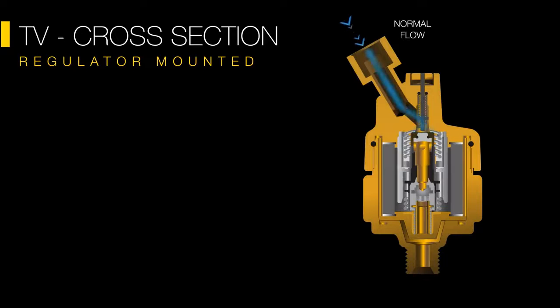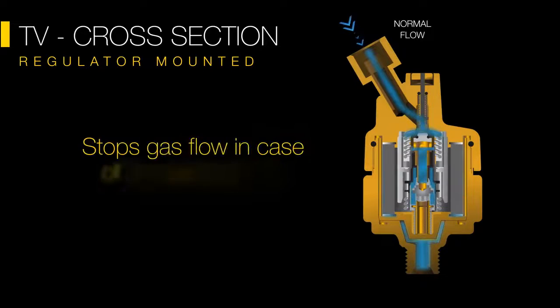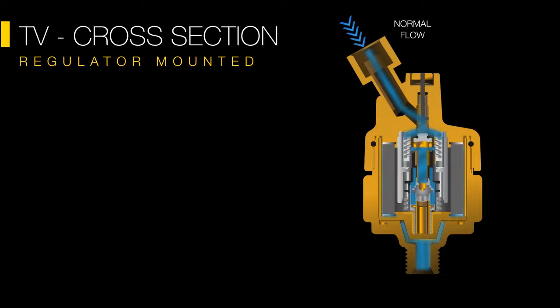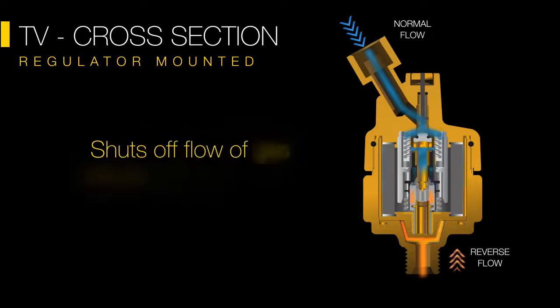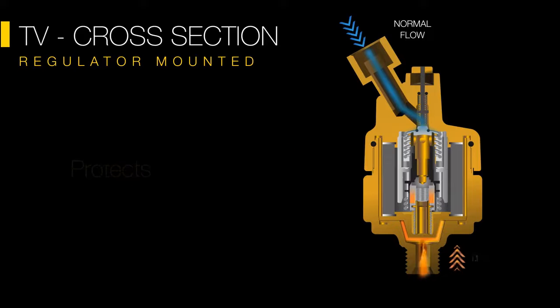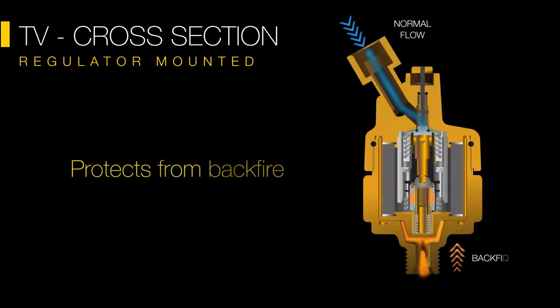The temperature sensitive valve allows free flow of gases as long as there is no temperature rise. It gets activated and cuts off flow in case of temperature rise beyond safe limits. The valve shuts off and arrests gas flow, limiting the flame from spreading.